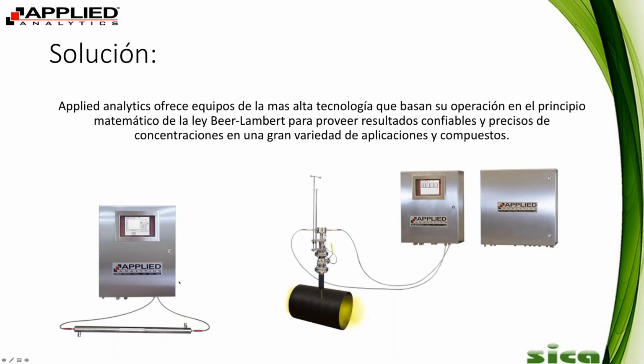So what you see here, basically on the left is the OMA with the flow cell, and on the right, what you see is the TLG with a UCP on the right, which would be the utility control panel, which would control your steam utilities, your instrument air, your nitrogen that would be used to, say, flush the probe or purge the analyzer, or control the steam that's used to remove the sulfur vapor in the purge, or in the probe, which I'll get to later.